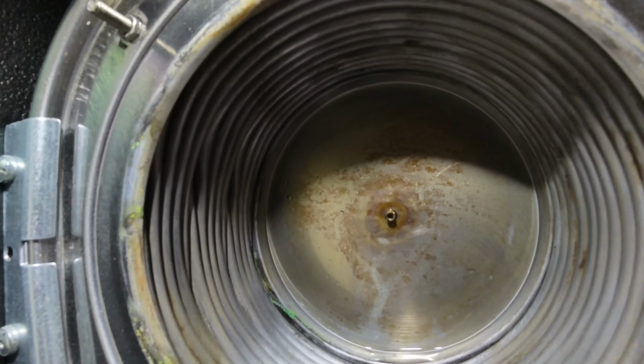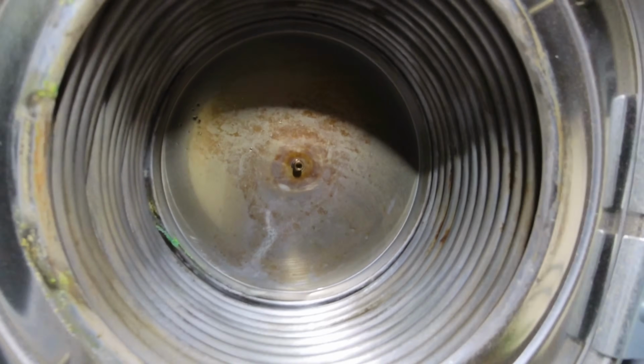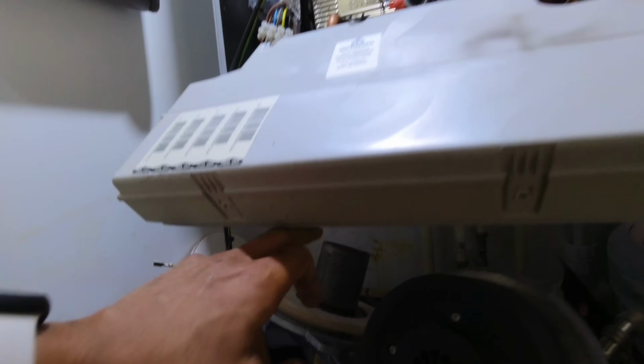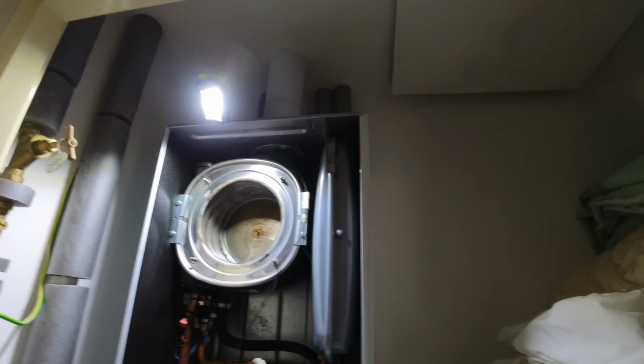Right, here we go, that is a lot cleaner than what it was before. Not that it was that bad before anyway. Yeah, that's all done. Going to put the rear insulation pad back on, change the G10 seal on that, clean up the electrodes, pop that back together, and then we can start doing our 26.9 checks.